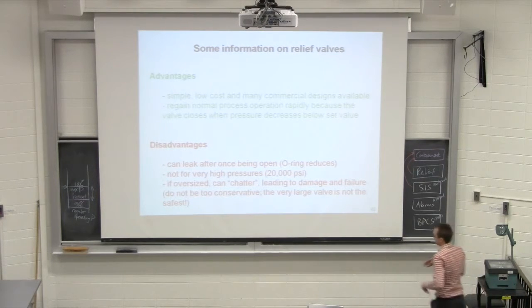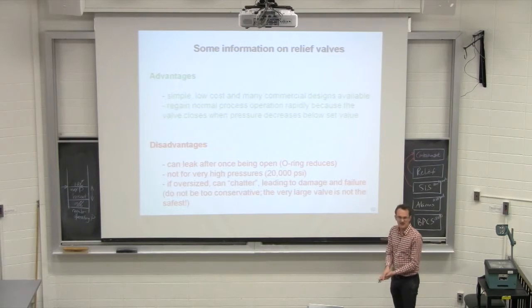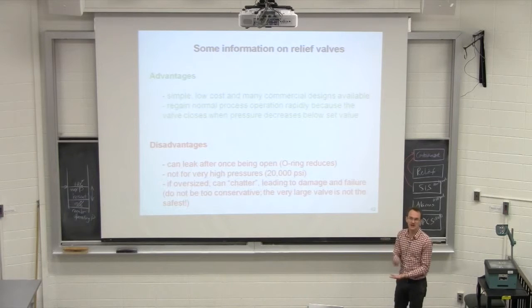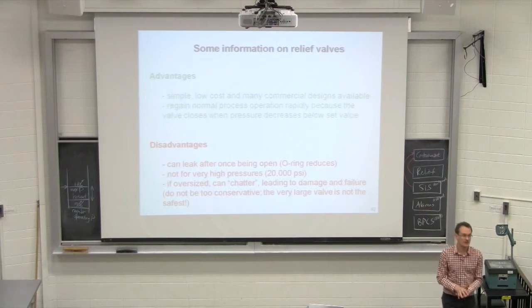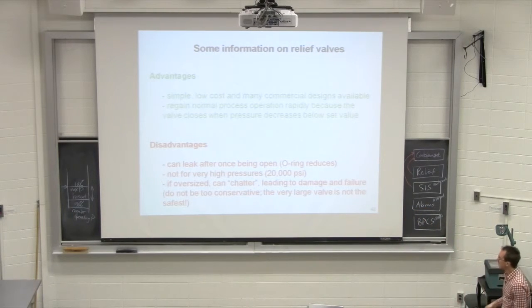There's a reason for it, right? Because when you're relieving, that valve is coming back down again. You're relieving, you're coming back down. And if you do that enough times, that valve doesn't always reseat itself. Okay, so it won't necessarily come back exactly to the right location. And you leave gaps in between, leading to constant leaks from your reactor. Now, if that's okay with you, that's fine.